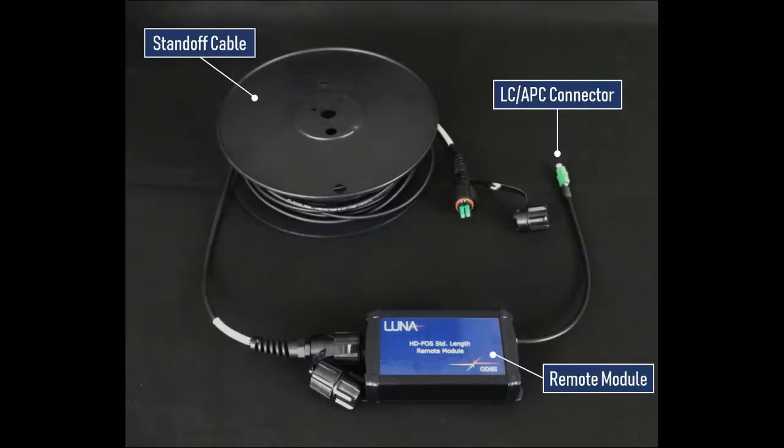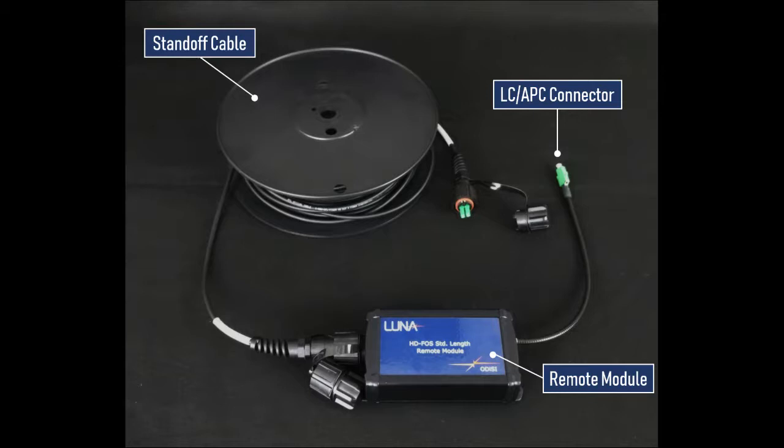A ruggedized standoff cable, either 50 or 100 meters in length, connects the interrogator to a remote module that allows the system to be kept a safe distance from any hazardous experiments. The remote module is where sensor optical measurements are taken and where any fiber optic sensors will be connected to the system.